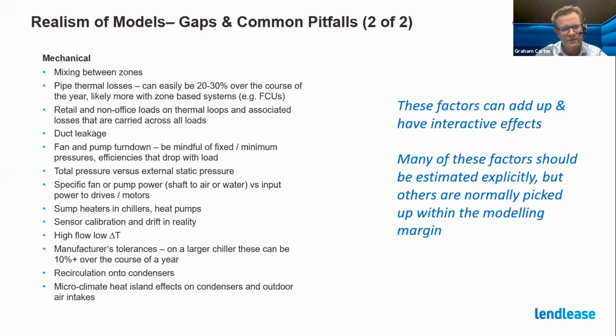to maintain high performance. High flow, low delta T, so pumping systems very rarely pump at the design range. They'll quite often be at a portion of that, and that can really impact your pump energy use, if not your plant efficiencies as you bring on more units to satisfy flow as opposed to the actual thermal load.